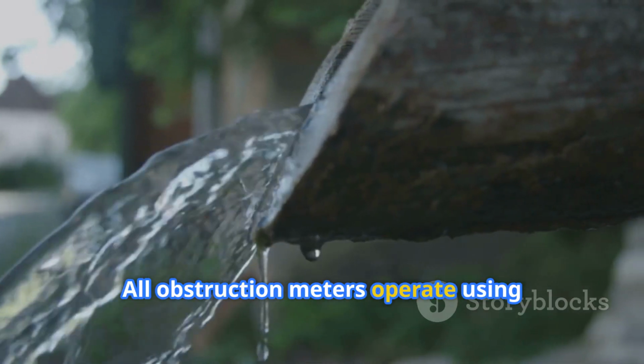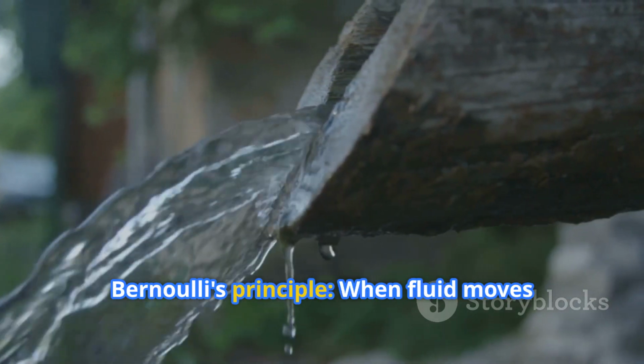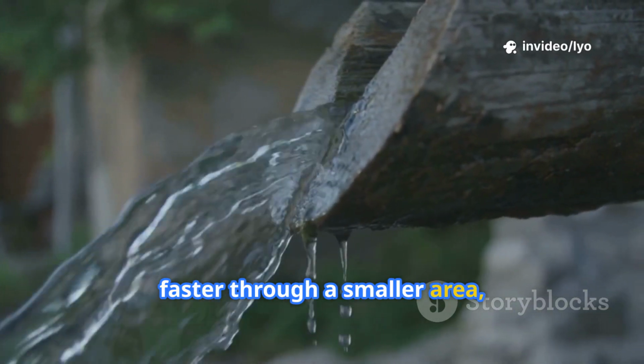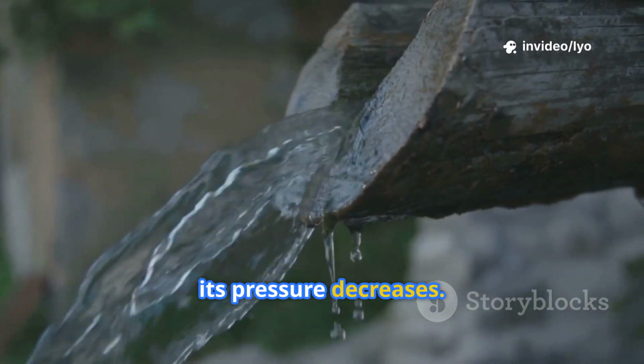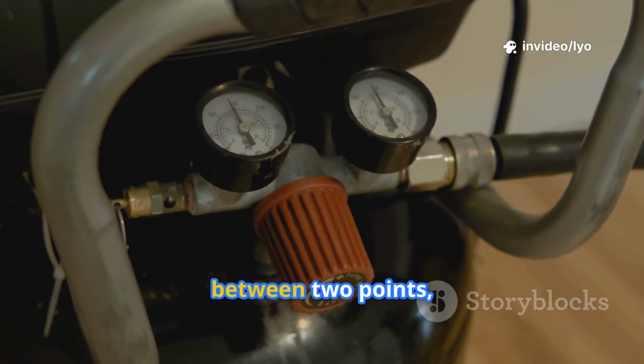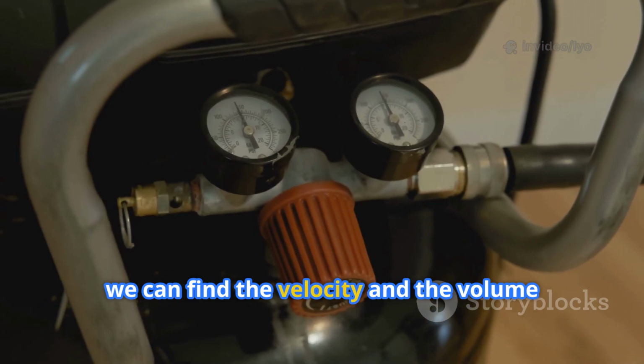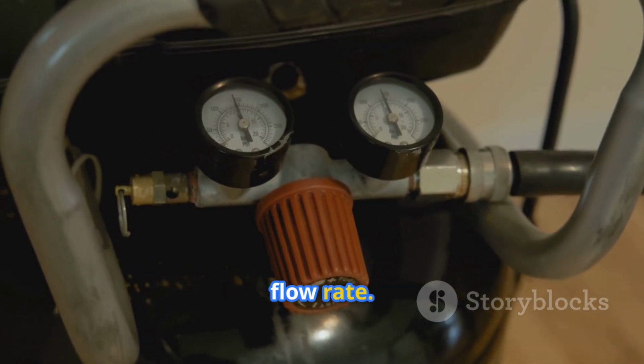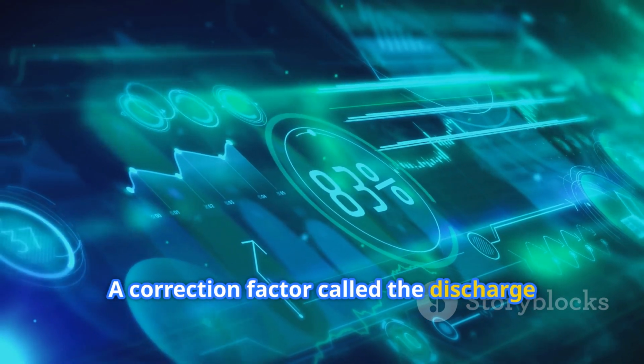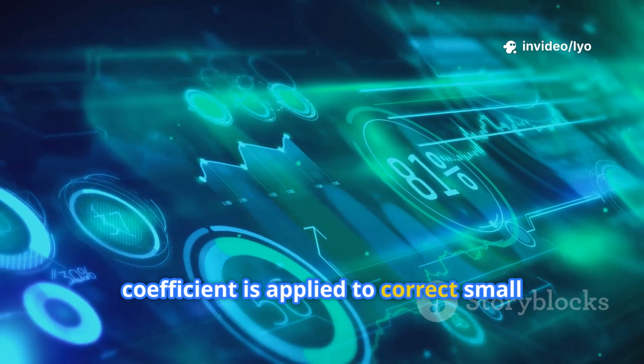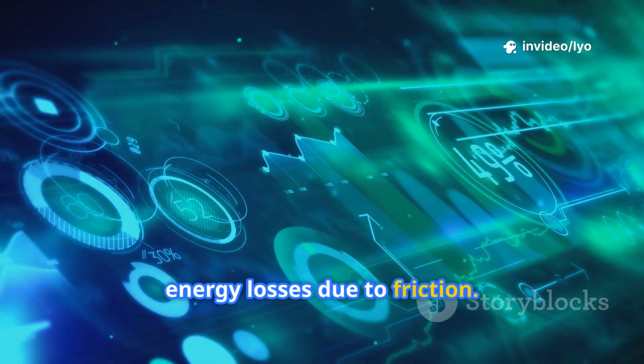All obstruction meters operate using Bernoulli's principle. When fluid moves faster through a smaller area, its pressure decreases. By measuring the pressure difference between 2 points, we can find the velocity and the volume flow rate. A correction factor called the discharge coefficient is applied to correct small energy losses due to friction.